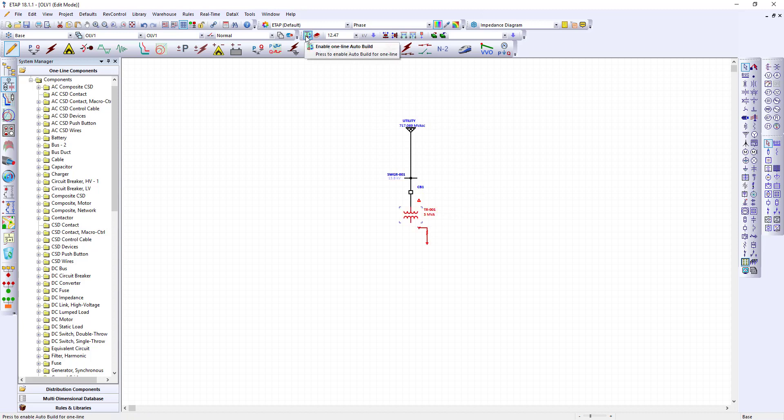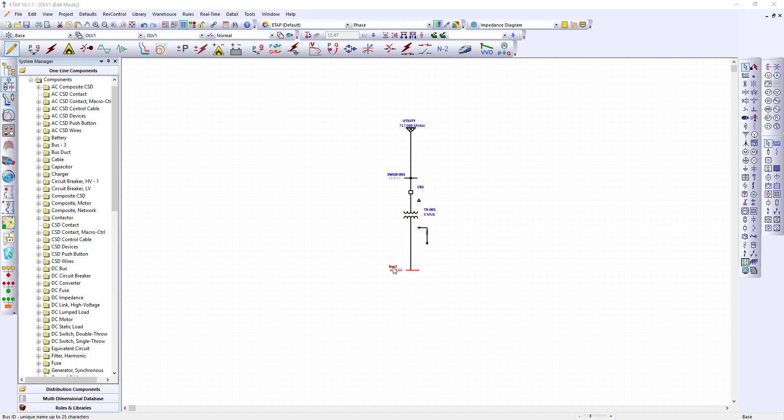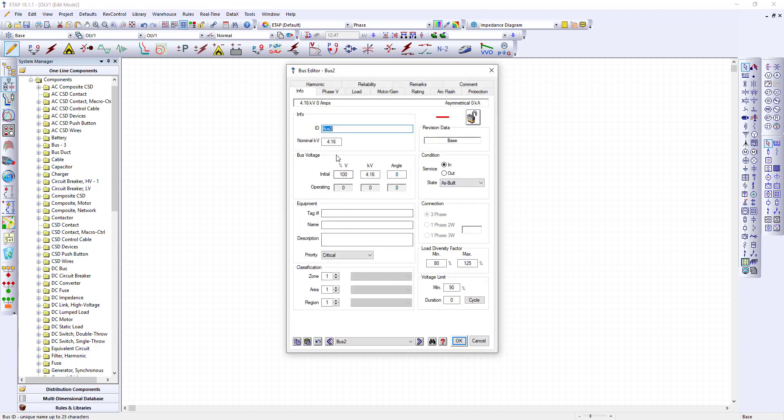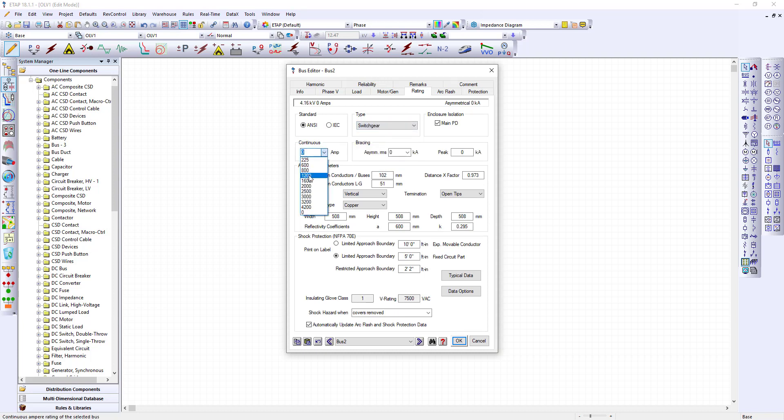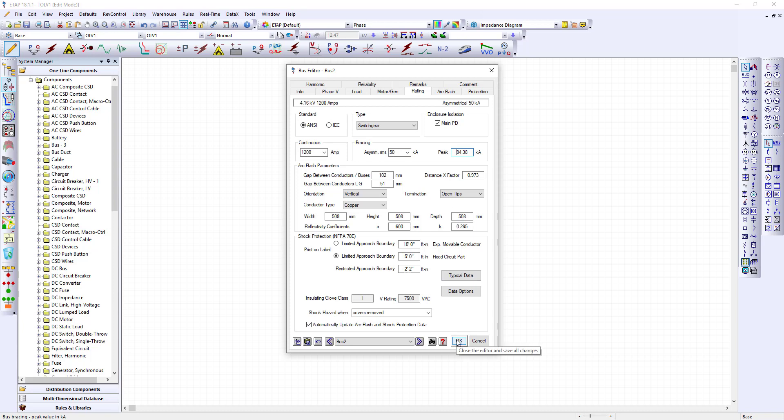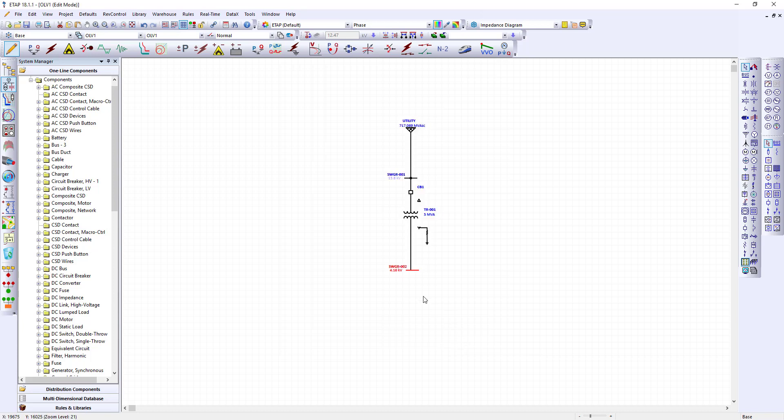I'm going to disable the auto build. Sometimes it gives you things that act funny. I will drag down from my pin to the next bus. Notice that this bus has changed to bus number 2 called switchgear SWGR-002 at 4.16 KV. Its rating will be a switchgear. We'll make it 1200 amp continuous. Again this will make it 50k.